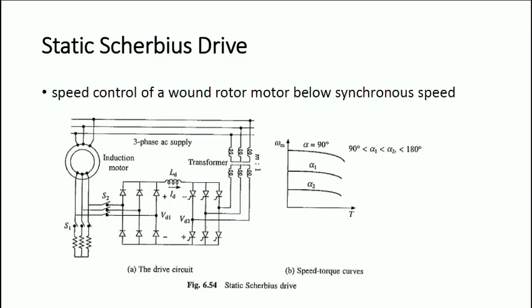The drive is started using resistance control: S1 is closed and S2 is open. When the speed reaches within the control range — for example, when slip falls to around 30% if S_max is 20% — the static Scherbius drive takes over: S1 is opened and S2 is closed. For fan and pump drives, braking is not required because the fluid pressure provides adequate braking torque, and the motor slowly comes to standstill.